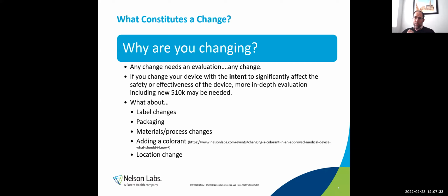So some of the changes we see, I talked a little bit about them. Label changes, believe it or not, even changing a label, we've seen impact on biocompatibility, and we'll talk about that in a little bit. Packaging, like I talked about, materials, process changes. For biocompatibility, there's the two things that we care about most when we look at a device. It's the material that it's made up of, and then any residuals from processing. Those two things are the two big things that we care about from biocompatibility.